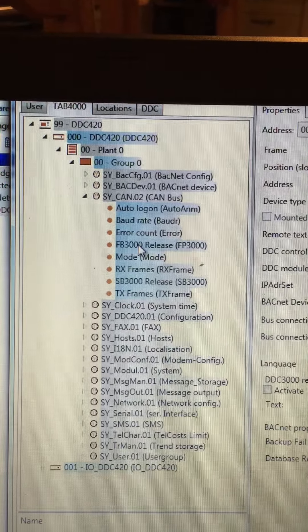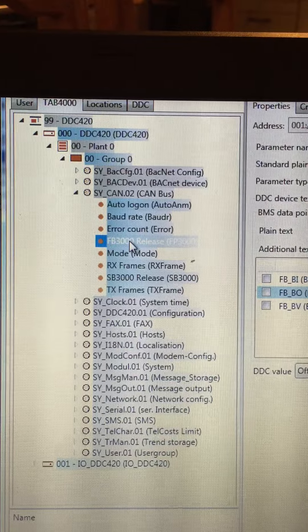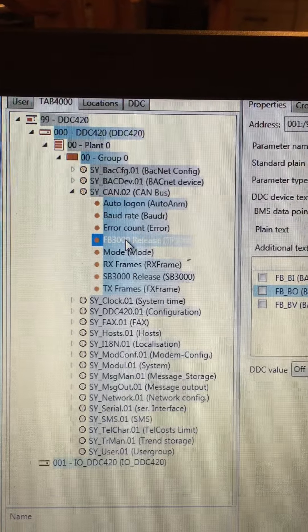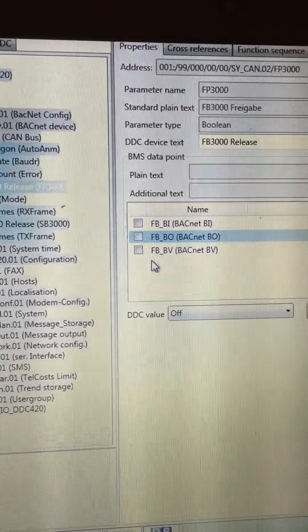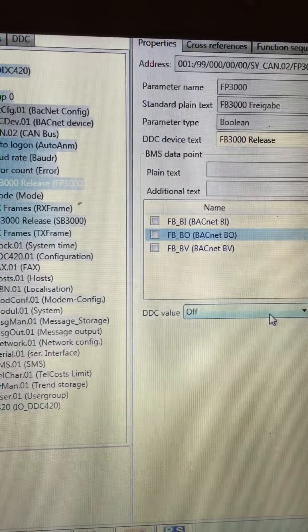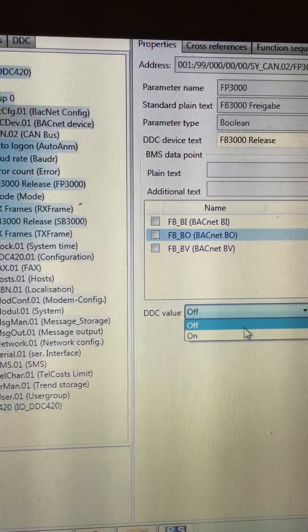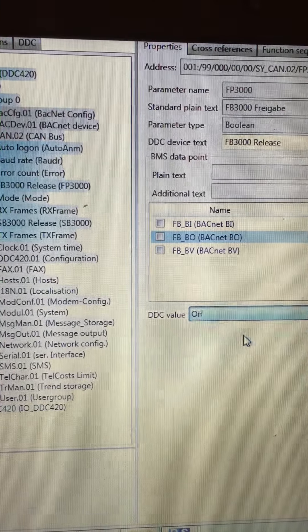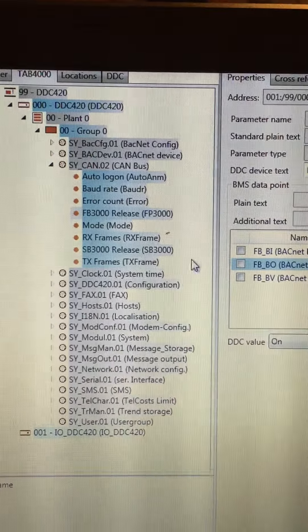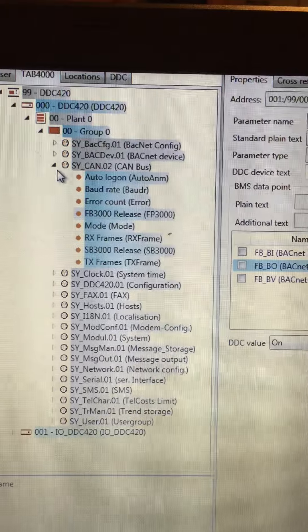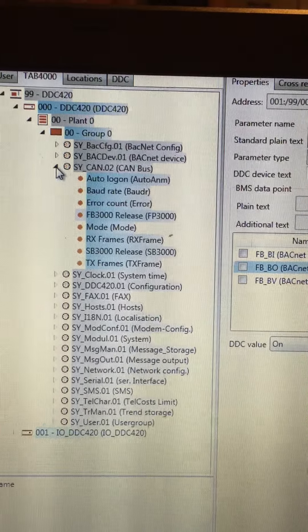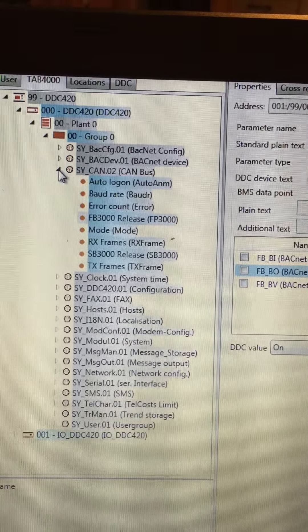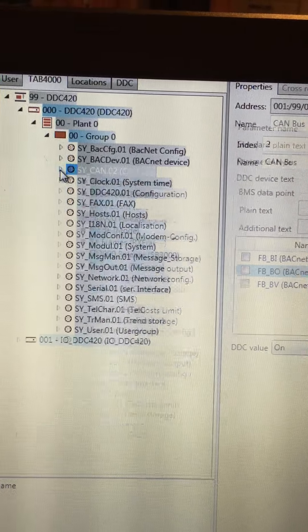I just double click on field bus 3000. And it opens up the group and I can set the value from off to on. This will allow my field bus modules to work. Again, if I'd made this download without making this change, it would not enable field bus.